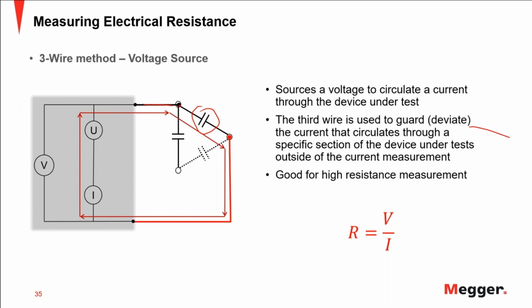I'm expecting to measure this current or leakage current. However, this is a current divider, and you're going to have more current being measured than what you are really circulating through your insulation. So you're going to get a result that is not accurate. The 3-wire method guards that measurement. So now you have an additional path for this current to circulate, and that current is not measured. The only measured current is this one here, which is the one that you are interested in.